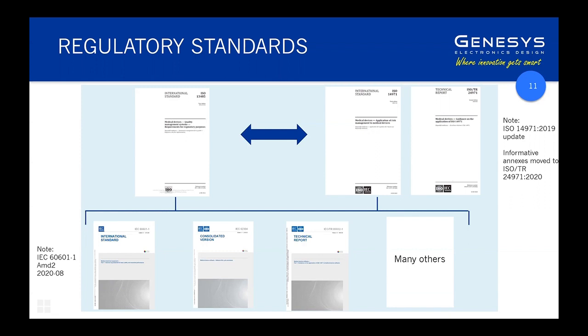The bottom line is, if you're going to do risk assessment or management for software against IEC 62304, it's almost essential that you refer to that companion technical report. So notice in the top right-hand corner, it's called guidance on application of 14971, or 24971, is it? Oh, yes, 14971.